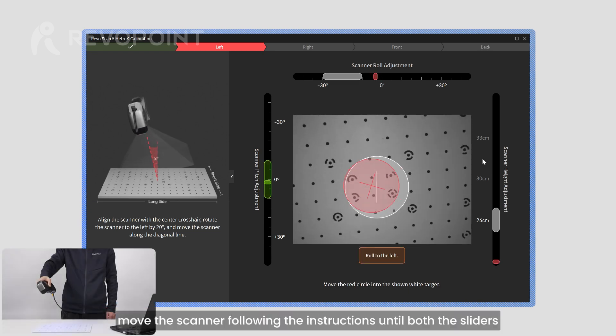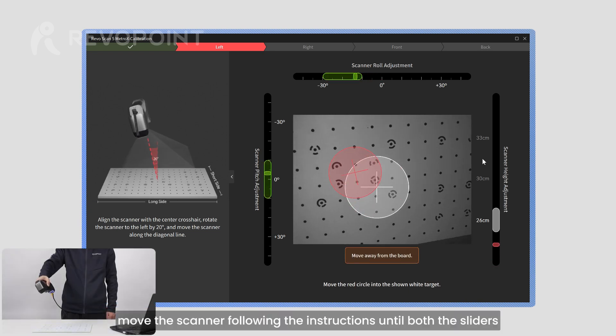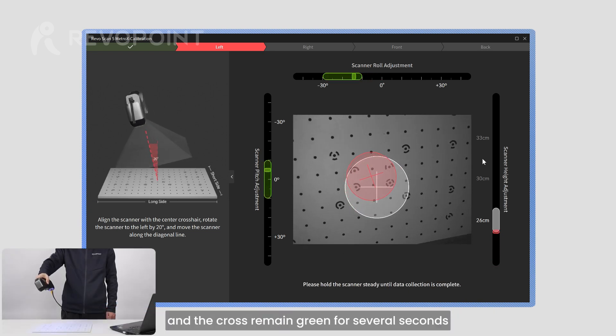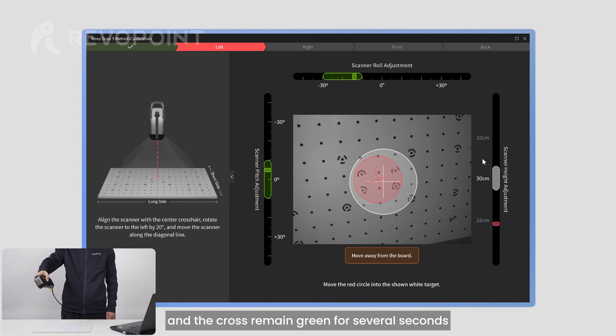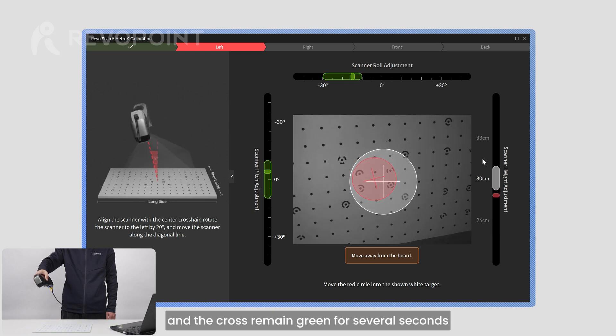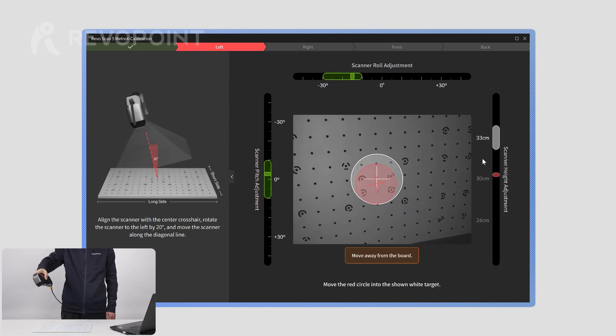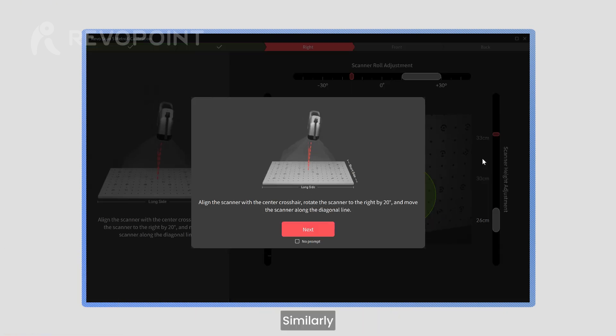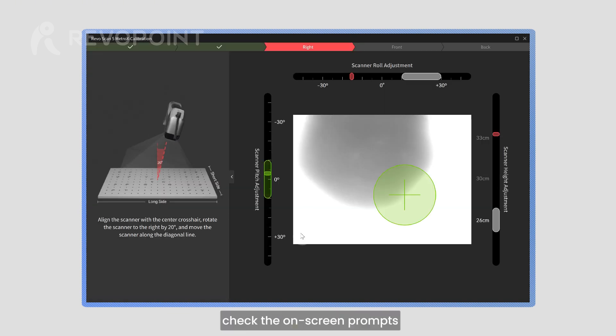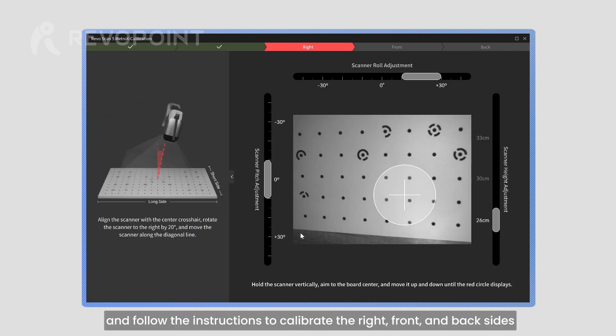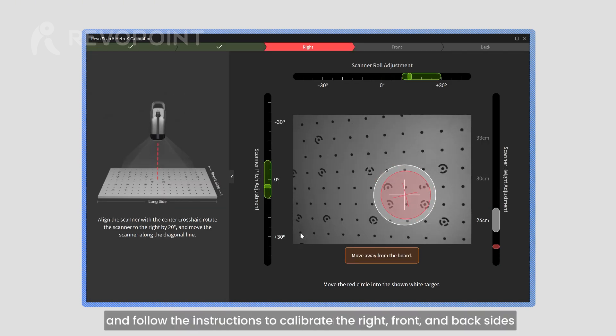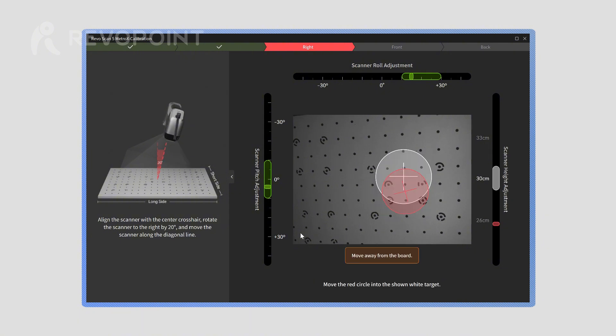Then, move the scanner following the instructions until both the sliders and the cross remain green for several seconds. Similarly, check the on-screen prompts and follow the instructions to calibrate the right, front, and back sides.